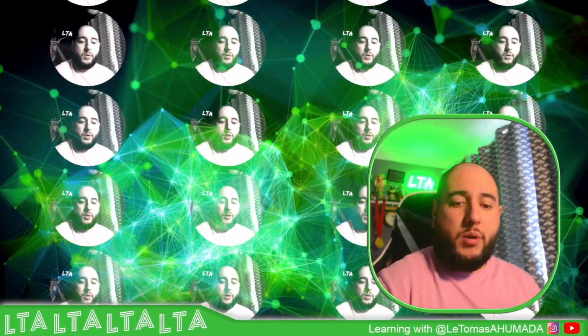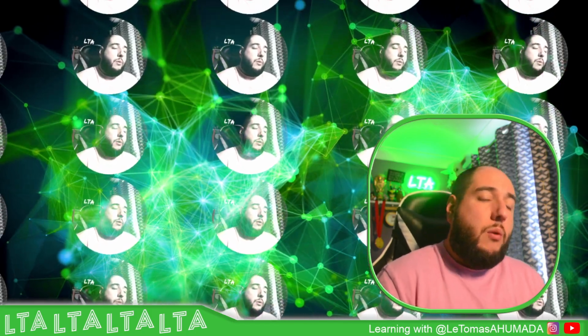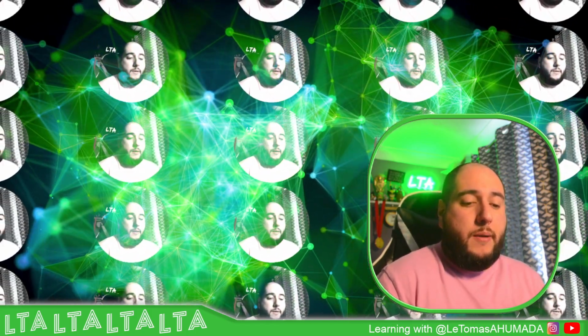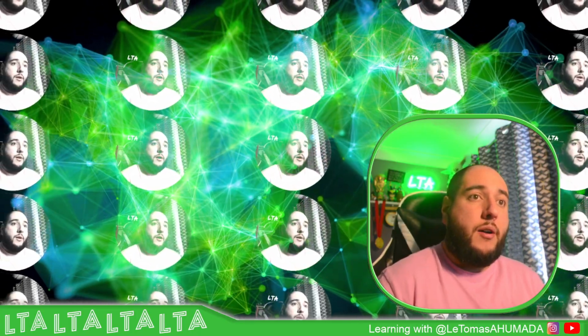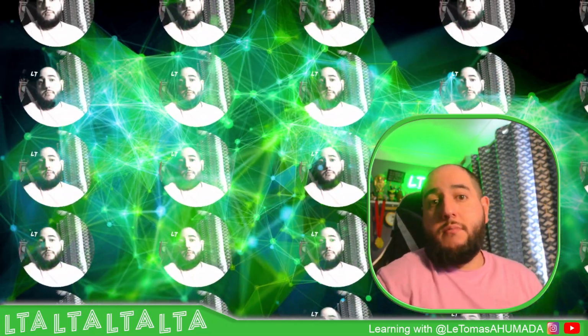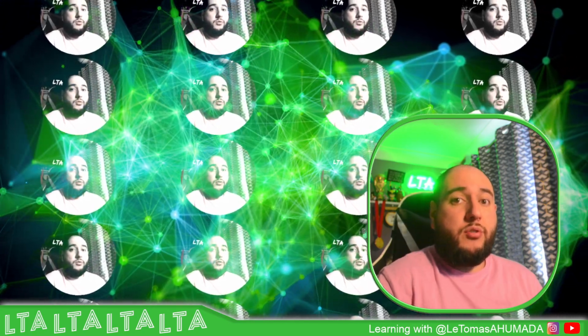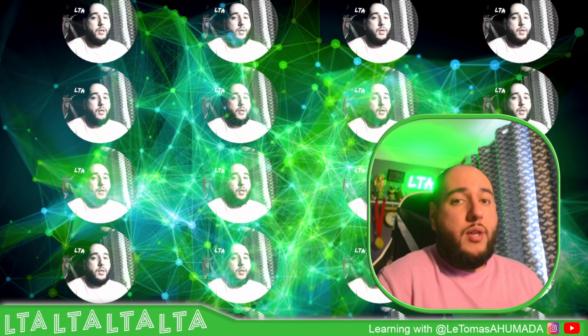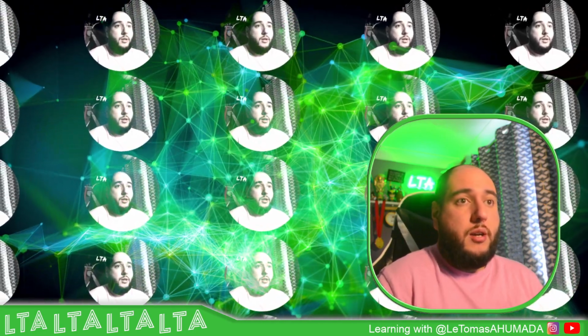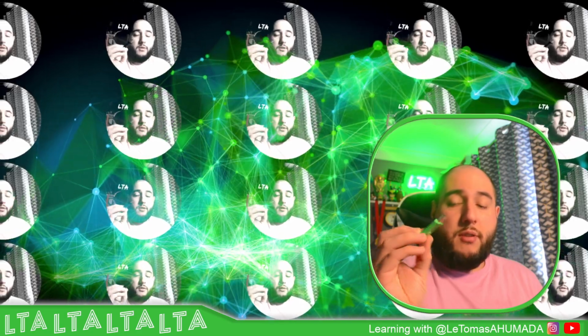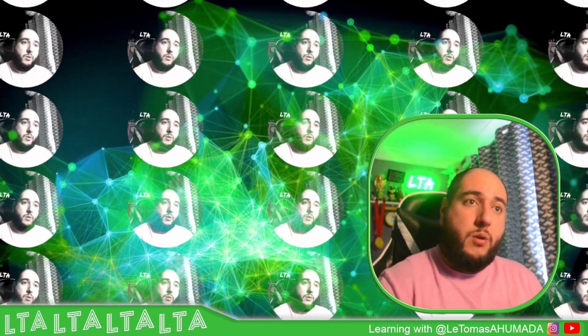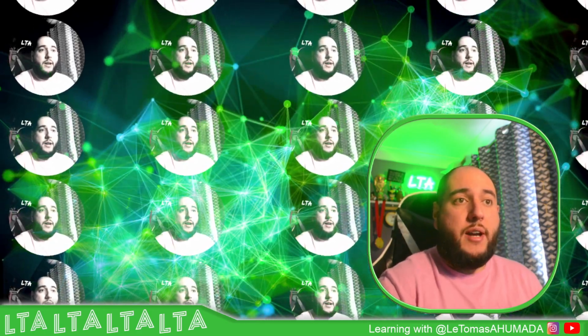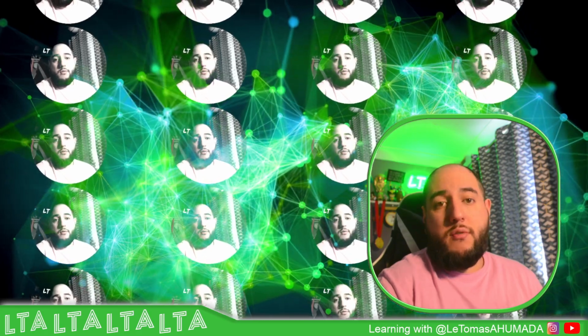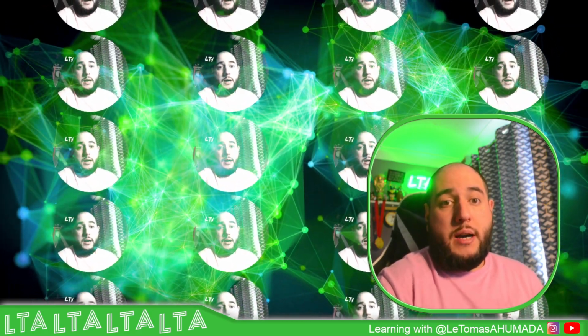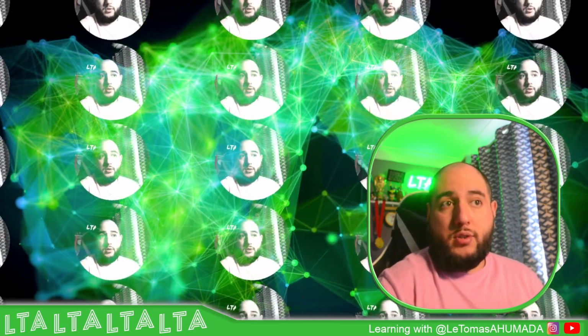So basically what I showed you in this video is how to download an application to an HMI that has a newer firmware. For example, if you buy a new HMI, you would probably have the latest firmware, probably Vijeo 6.3. So if you need 6.2, then what you need to do is to use a USB stick, download the files into the USB, plug it in, and install the files. That probably is going to be only the runtime for 6.2 and the files for the application. Okay, so that should be it.